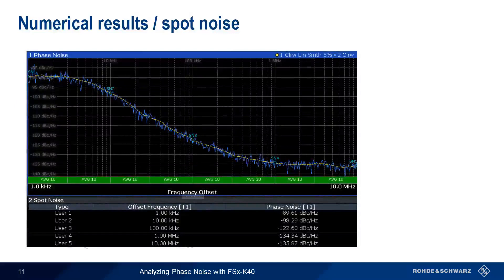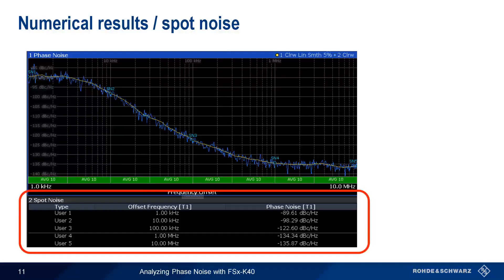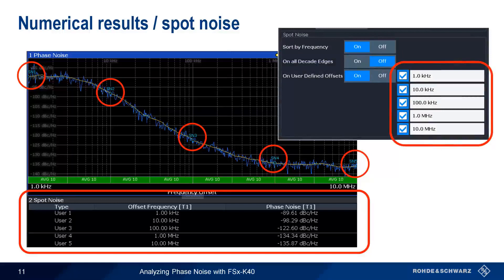If we're interested in the phase noise at a specific frequency offset, this is called spot noise, and is often used when verifying that phase noise is below a certain specified level at a given offset. Spot noise is often displayed as a table of offsets and phase noise values, with markers automatically placed at corresponding trace points. By default, spot noise values are measured at decade edges — that is, at different powers of 10, for example 1 kHz, 10 kHz, 100 kHz, etc. — although these can be easily changed by the user.